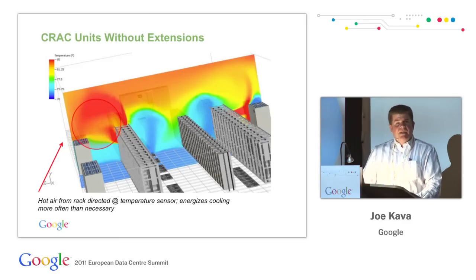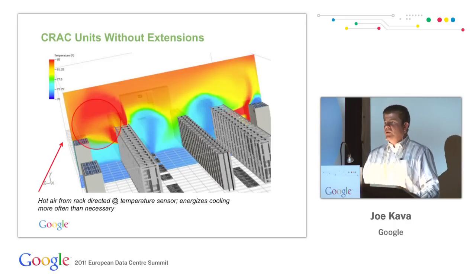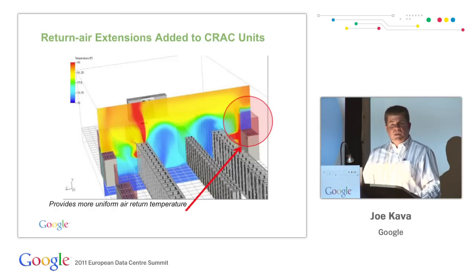I mentioned that we added these 1.2 meter tall return air extensions to the CRACs. This is what the thermal profile looked like without the extensions. On the left side of this picture, you'll see where the hot spots were in this room. That was because these higher density racks were really discharging right into that CRAC unit there, you can see. So with the extension, on the right side of this room, you see this picture where now we have a much more balanced temperature distribution.